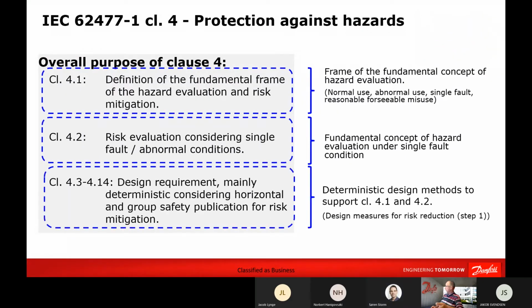Yeah, the last things here - just an overview of 62477. Clause 4 is the design. Clause 4.1 and 4.2 give you the high level or fundamental concepts of hazard evaluation. 4.1 covers normal use, abnormal use, single fault, reasonably foreseeable misuse. 4.2 is the single fault condition. The rest of clause 4 is some deterministic design methods that can be used to achieve risk reduction through your design.